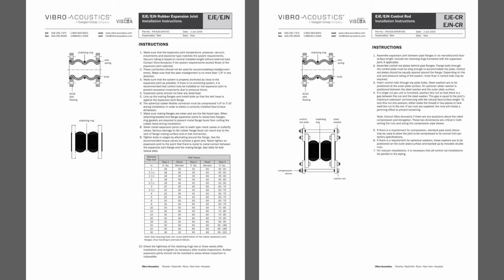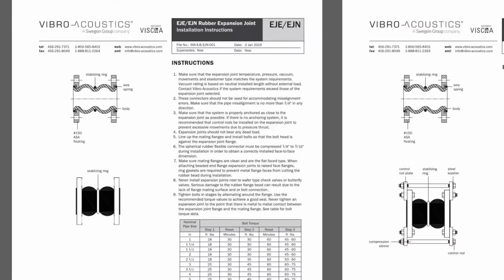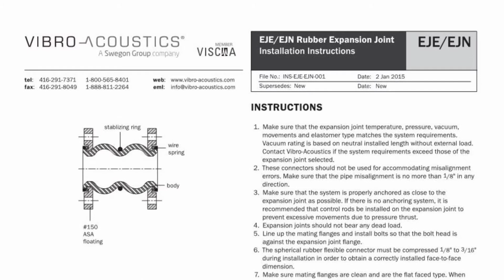Moving over to the installation instructions now, we'll focus on things we can check during a site visit. We have separate installation instructions for with and without control rods, so since this joint did not have them, we'll look at those instructions. First, make sure it's the right expansion joint in the right place. Check joint material, fluid pressure, and temperature. As long as the piping system is serving typical HVAC systems, you usually don't have to worry too much about pressure and temperature.